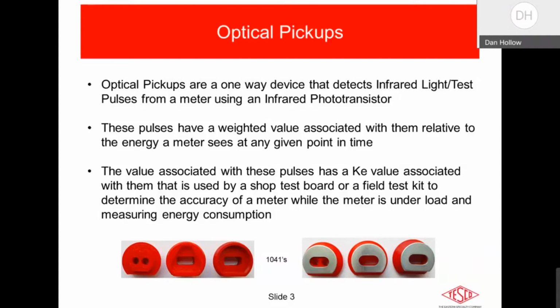There are some meters out there still in the industry that do not have metal plates on the front of the meter. So those meters typically have a raised plastic ridge. Sometimes they're triangular, sometimes they're semicircular. And in those cases, there are adapters like these 1041s down here that will allow you to put these adapters on those types of meters that don't have the metal plate, because optical probes have a magnet in the head that sticks to the metal plate on the front of the meter. If the metal plate doesn't exist, you can use these type of adapters to put them on those meters to give them the metal plate.